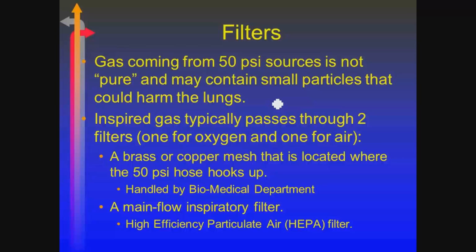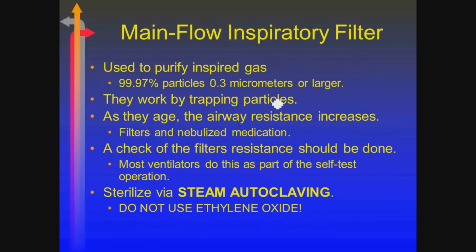Talked about these brass ones and the HEPA filter. Key part to remember with these is that these filters work by filtering, meaning that they trap particles. So eventually, a filter's efficacy goes down because it's being clogged up. But as it's being clogged up, it also increases the airway resistance. So it's a double-edged sword there. I'm filtering the gas, but in filtering it, I'm also potentially increasing the airway resistance. Most ventilators have a self-check internally that they'll be able to determine if that filter is going bad and what you need to do about it.